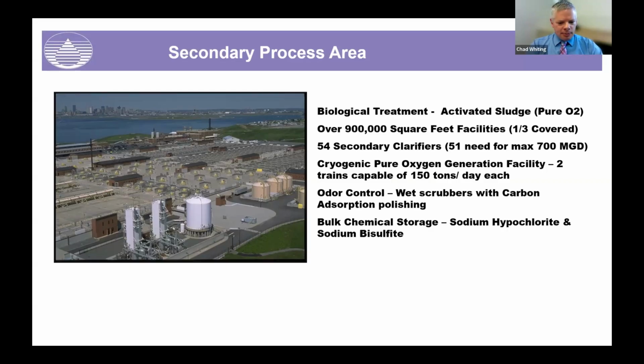So we add the sodium hypochlorite to do the disinfection process, where we need at least 15 minutes of contact time. Then as the water leaves the disinfection basin, it drops into a 420-foot drop shaft, where we turn a hydroturbine generator. We take advantage of that elevation change and turn a 1 megawatt hydroturbine generator prior to it going out to the outfall. But we also add the sodium bisulfite 870 feet into that tunnel to take advantage of that space for additional disinfection time that we need in our max capacity flows.